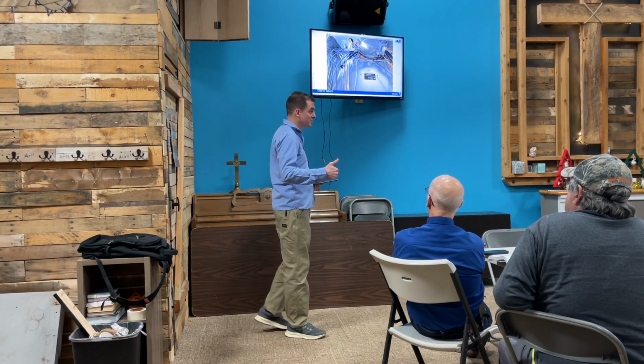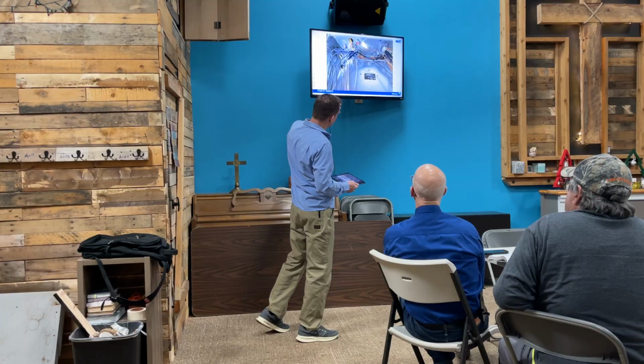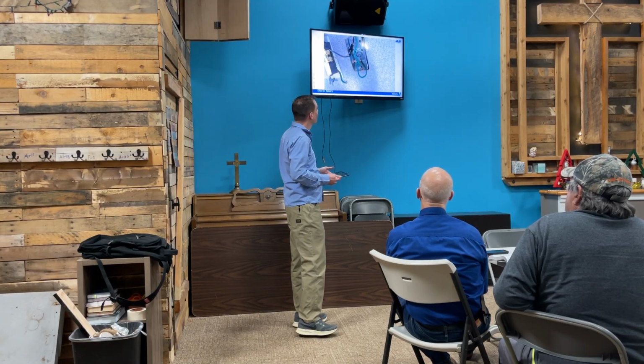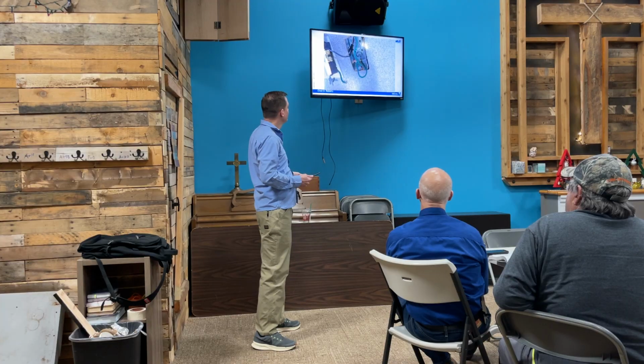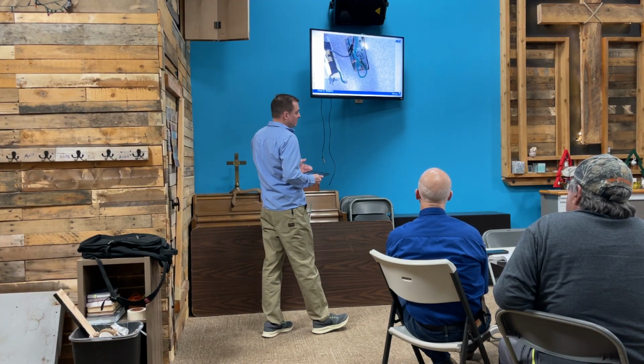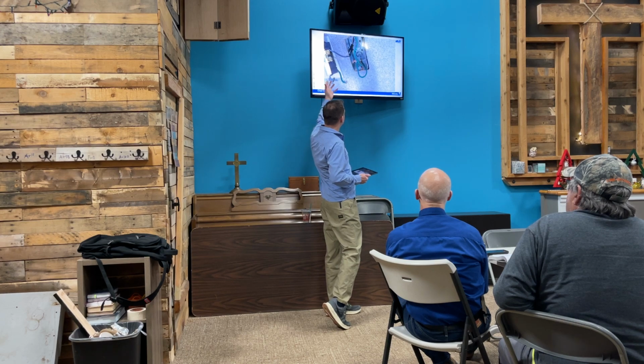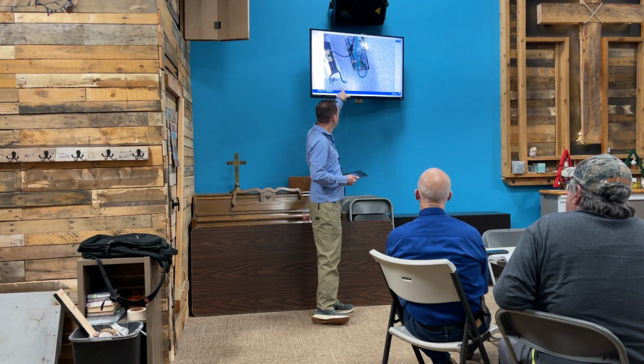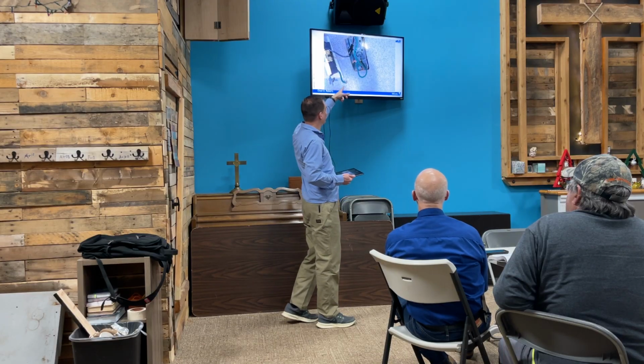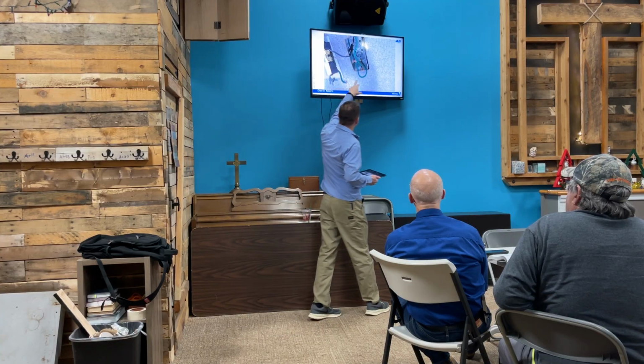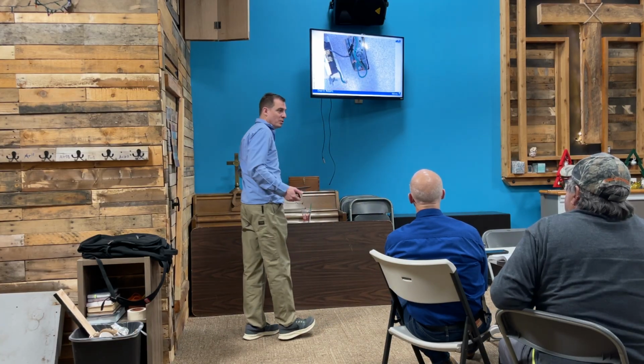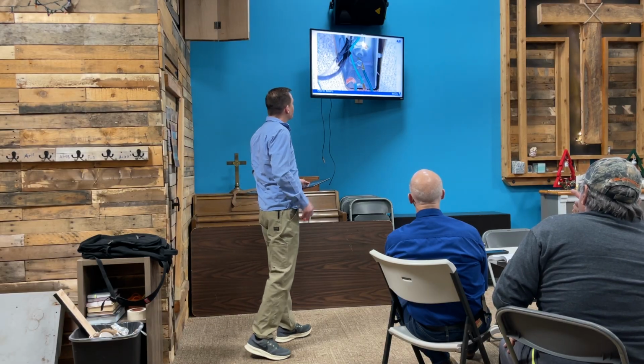So you inspectors, how far you want to go is kind of up to you, but look at what's behind the walls of these things. The first one's not a big deal, not too scary. You could stand a clamp on that cable, the yellow cable coming in. So I pulled this receptacle out, the connection fell apart immediately, and I could tell by the screw head that this is not a machine screw, just some kind of whatever screw they had laying around. The router cut the cable.